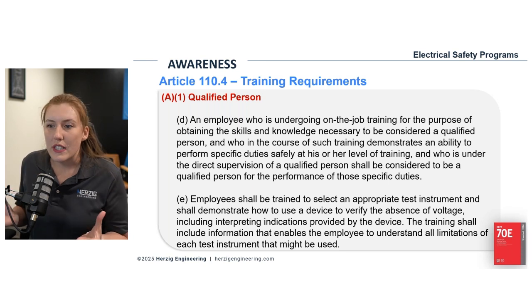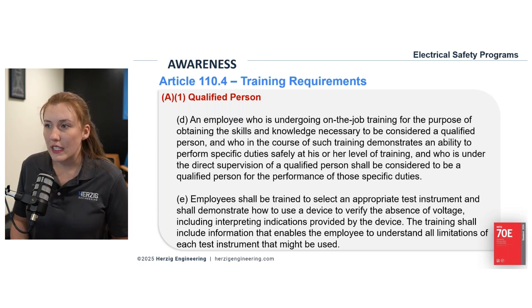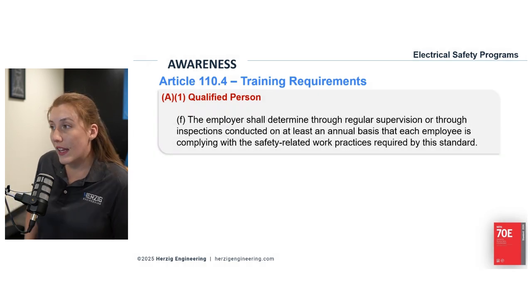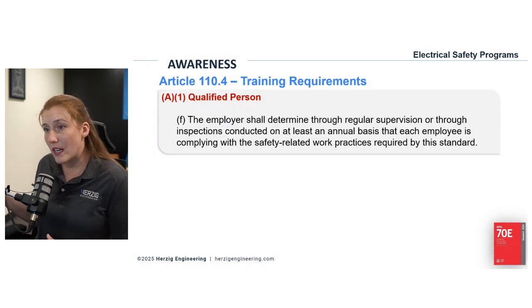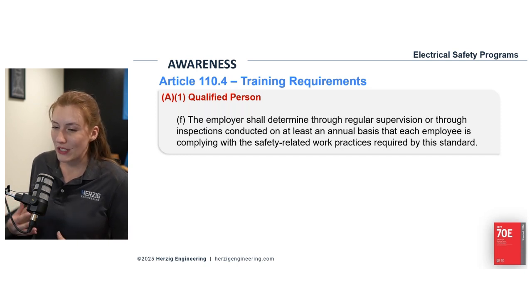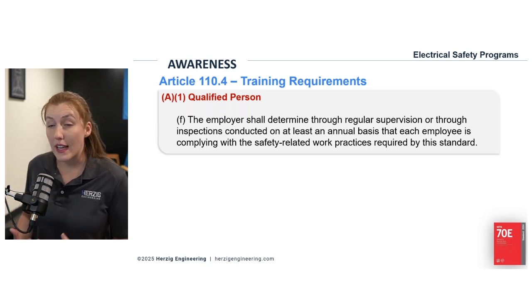There's additional steps. The point is verification of absence of voltage: live, dead, live check, known dead, known source with your meter. That's a very key part of electrical safety training.